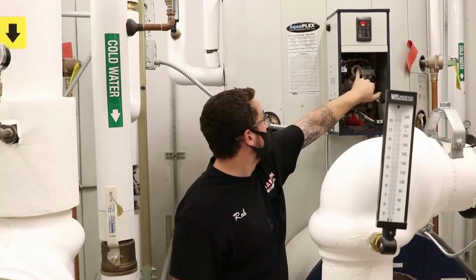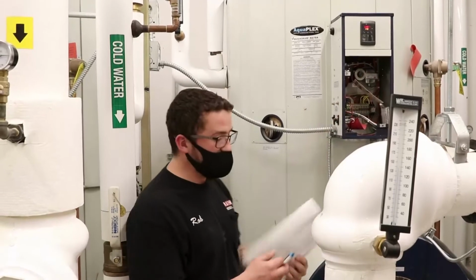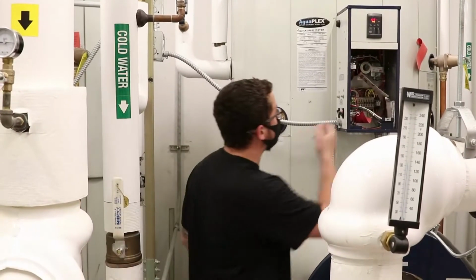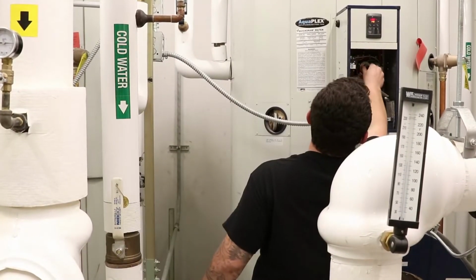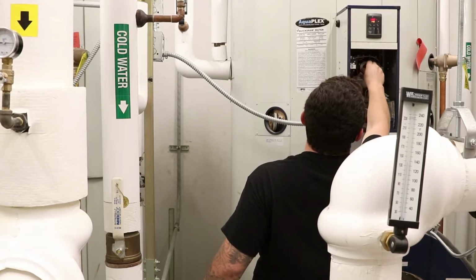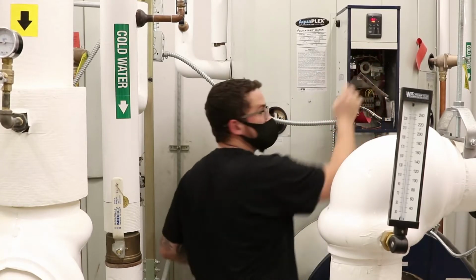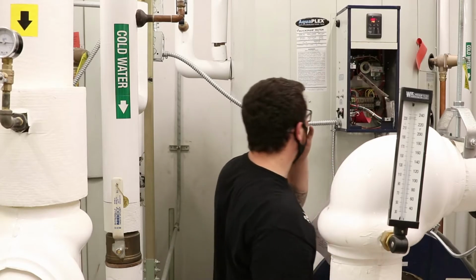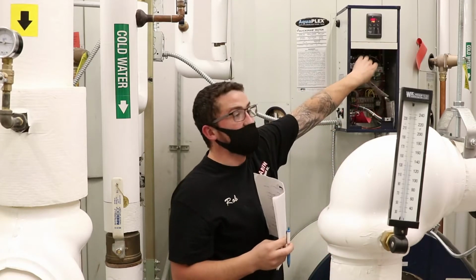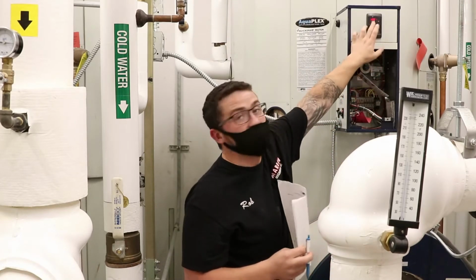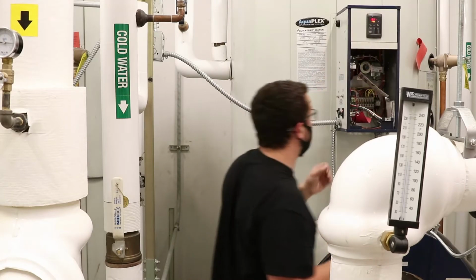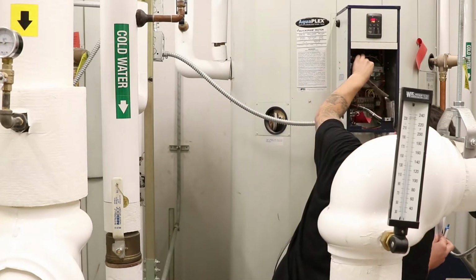This control clicks when it opens and closes. So if you touch this dial, you'll hear the control open and close, and that should happen when the indicator is on the dial at the temperature that's in the tank. You'll be able to tell whether that's accurate or inaccurate based on when it opens and closes.